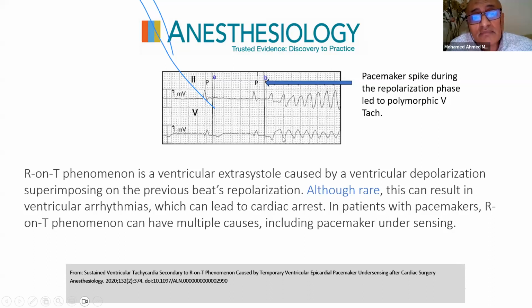So this is an example that we have to maintain the defibrillator pacing electrodes and keep the patient monitored during the post-operative period until the device is examined by the CIED team and they confirm that the device returned to its normal function. In this case, by removing the magnet, the device did not return to its synchronous pacing rate of 80 beats per minute. It remained in asynchronous pacing at 100 beats per minute.